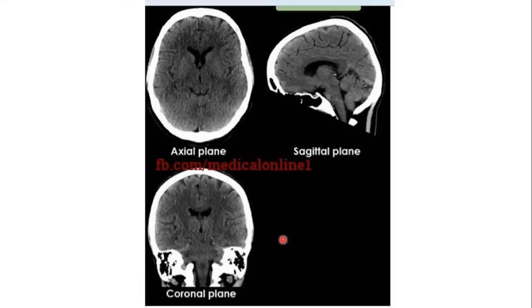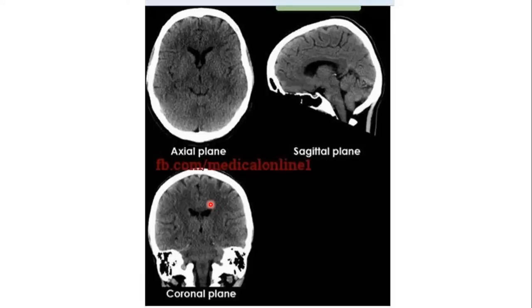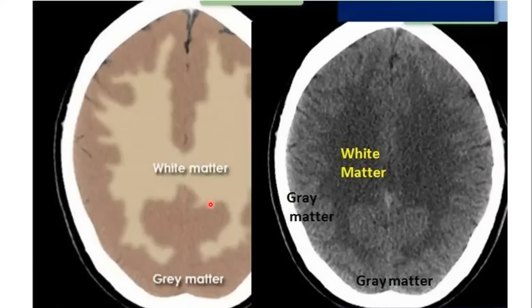The CT scanner acquires brain images in the axial plane. If thin slice thickness — for example one or two millimeters — is used, the computer can reconstruct the images into sagittal and coronal views. The machine does not acquire sagittal or coronal directly; we acquire axial images but use thin slices to enable reconstruction. The thinner the slices, the better the reconstruction quality.